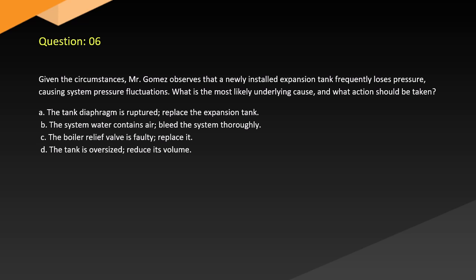Question 6. Given the circumstances, Mr. Gomez observes that a newly installed expansion tank frequently loses pressure, causing system pressure fluctuations. What is the most likely underlying cause and what action should be taken? A. The tank diaphragm is ruptured. Replace the expansion tank. B. The system water contains air. Bleed the system thoroughly. C. The boiler relief valve is faulty. Replace it. D. The tank is oversized. Reduce its volume.